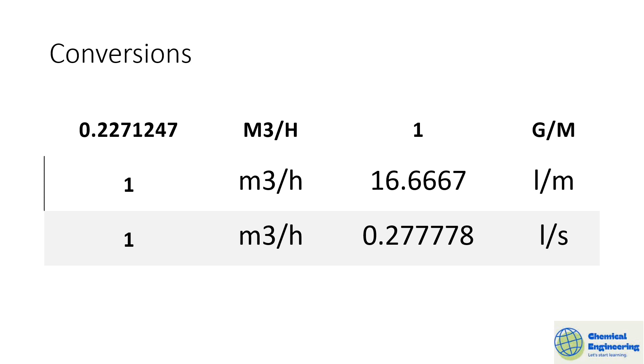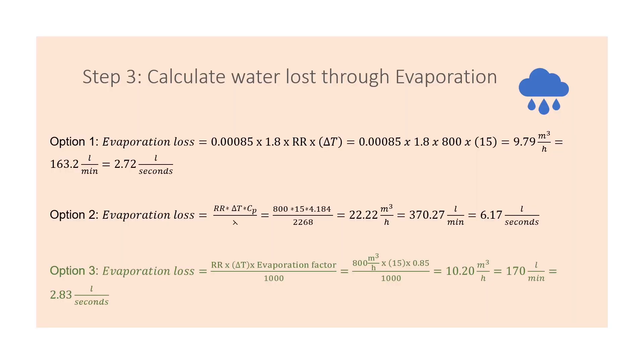There's various equations that you can use here. The first equation, let's look at it. It has a factor of 0.00085 multiplied by 1.8 and the circulation rate. Our circulation rate here we can estimate it to be 800 multiplied by the temperature difference. Punch everything into your calculator and you get your answer in form of meter cubed per hour. You can also get it in the form of liters per min or 2.72 liters per second.